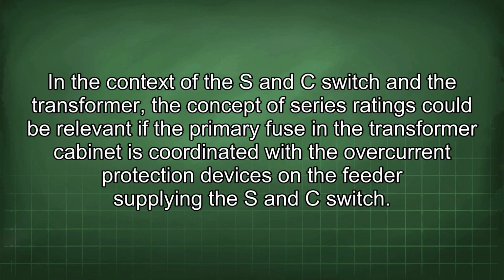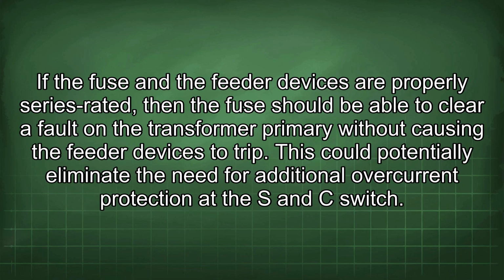In the context of the S and C switch and the transformer, the concept of series ratings could be relevant if the primary fuse in the transformer cabinet is coordinated with the overcurrent protection devices on the feeder supplying the S and C switch. If the fuse and the feeder devices are properly series rated, then the fuse should be able to clear a fault on the transformer primary without causing the feeder devices to trip. This could potentially eliminate the need for additional overcurrent protection at the S and C switch.